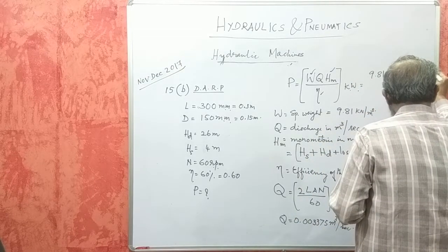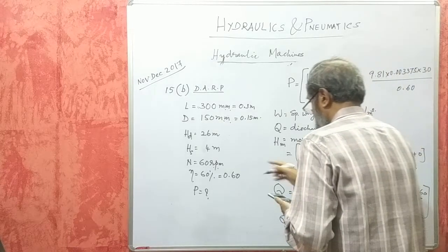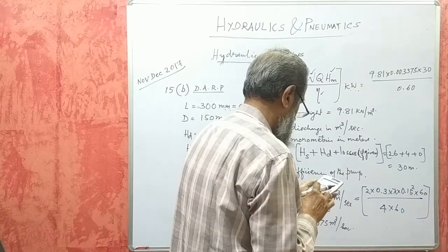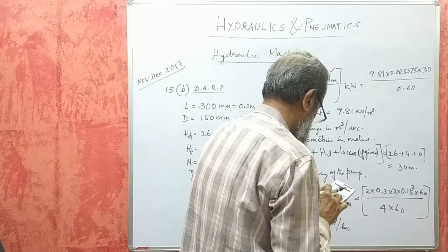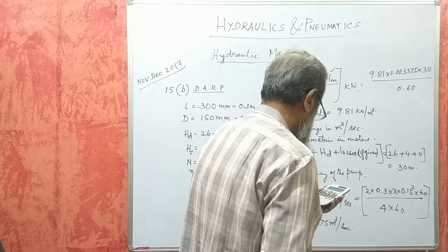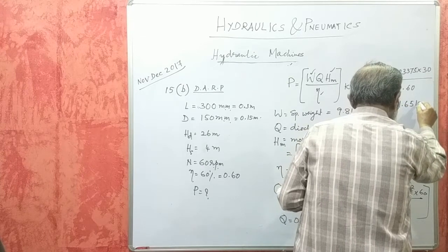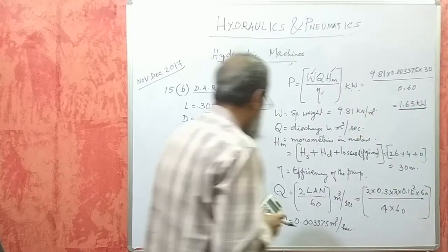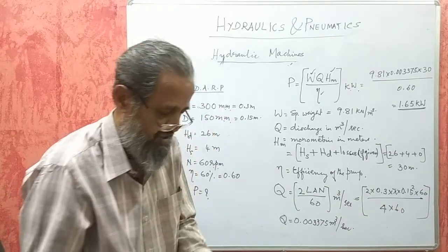W is 9.81, Q is 0.003375, HM is HS plus HD = 26 + 4 + 0 = 30 meters. So P = 9.81 × 0.003375 × 30 / 0.60, which works out to 1.65 kilowatts. This is the power of the motor required to drive this pump to deliver that discharge through that height.